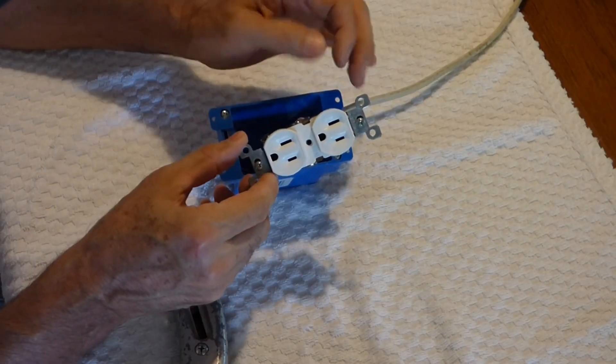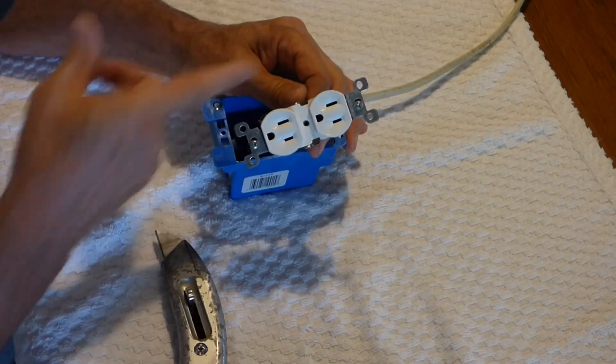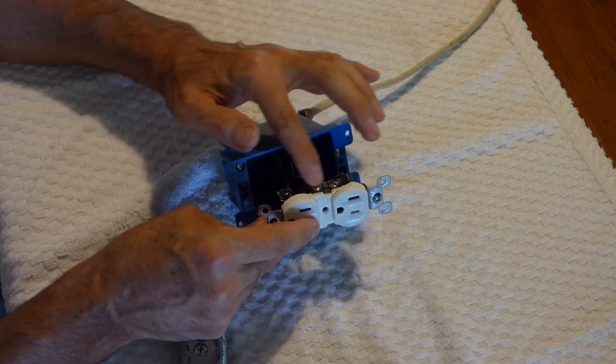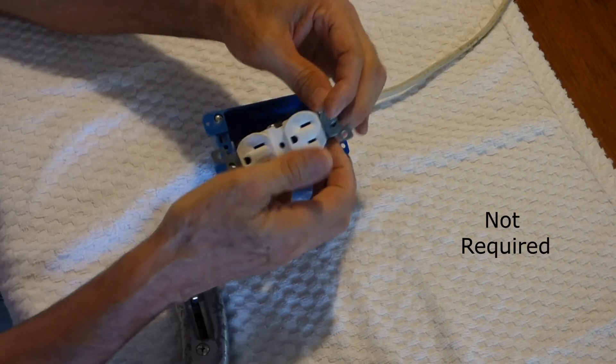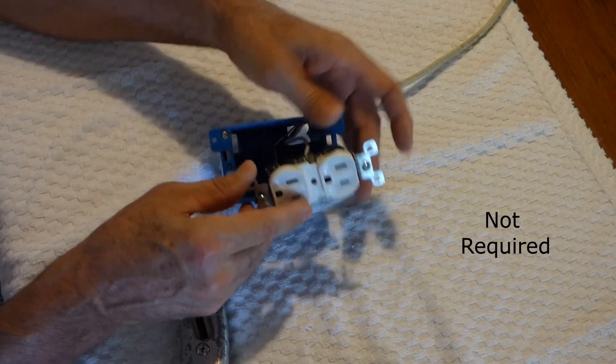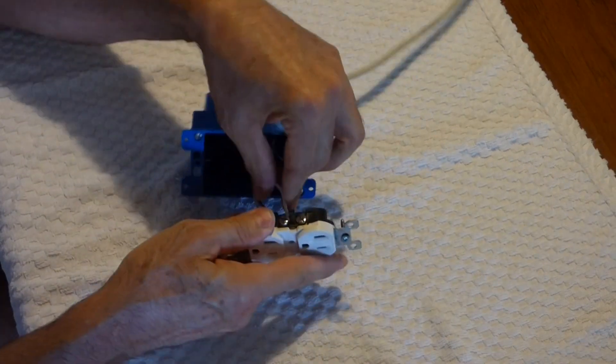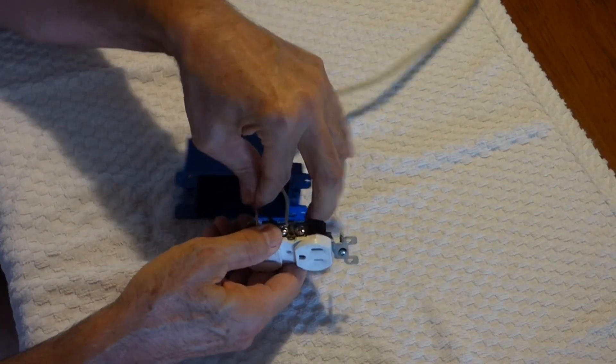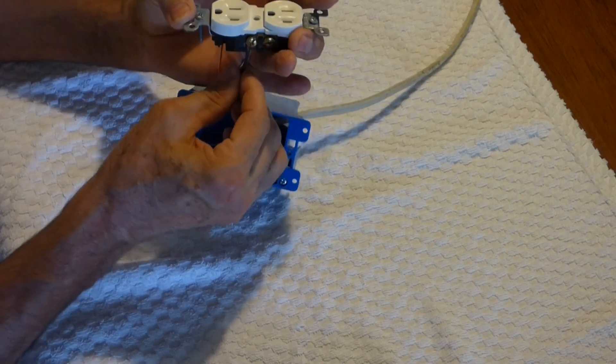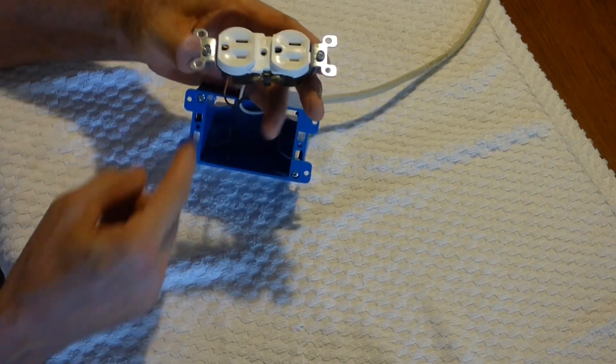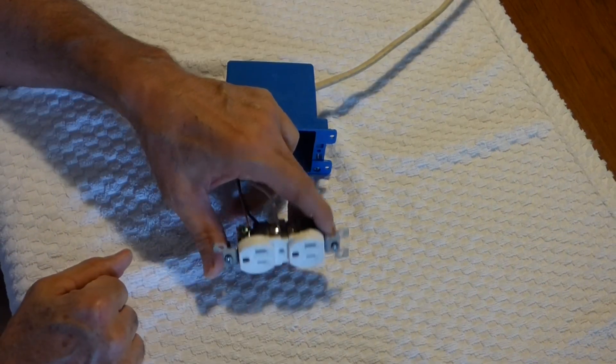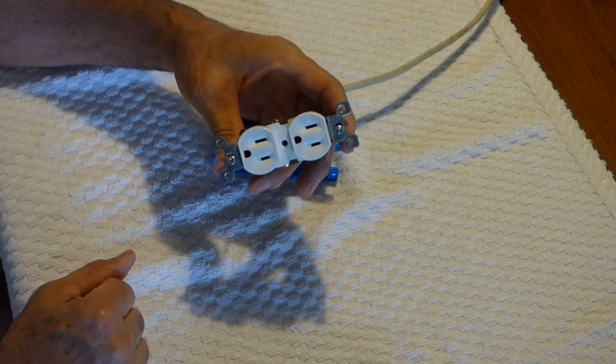Some electricians also, after they get these wired like this, they like to take electrical tape and tape around these connections to ensure there's no contact. You want to make sure these wires are tight, not loose at all. If you get a loose wire, you can get an overheating problem, and it can also cause a fire.